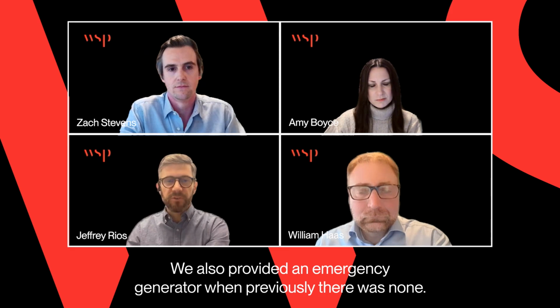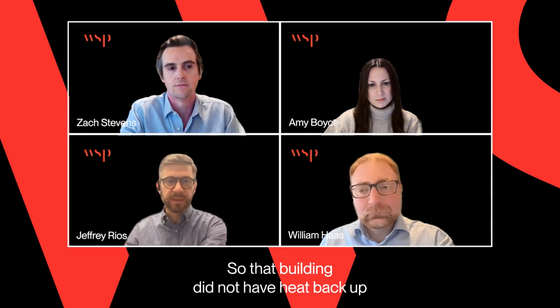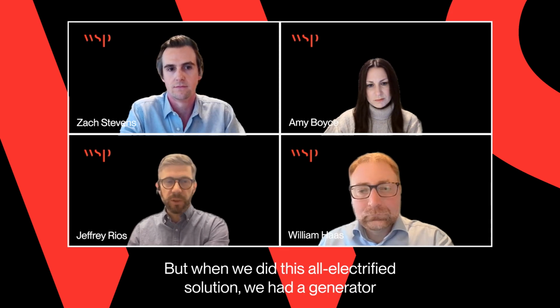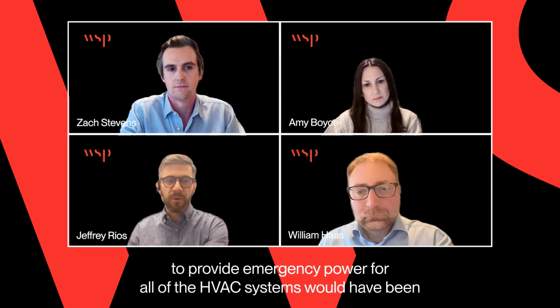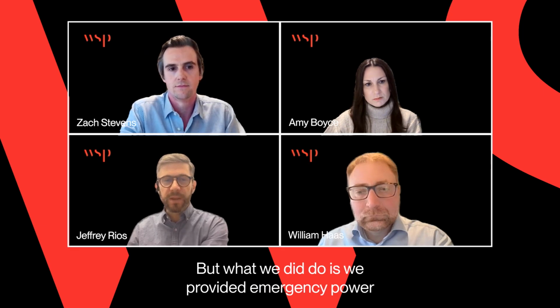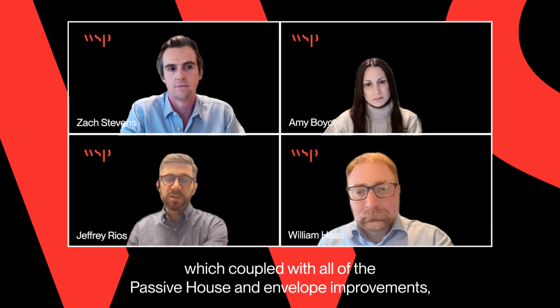We also provided an emergency generator when previously there was none. So that building did not have heat backup in the event of loss of power previously. But when we did this all-electrified solution, we had a generator to provide emergency power for all of the HVAC systems — that would have been a super big generator that frankly we didn't have the room for.